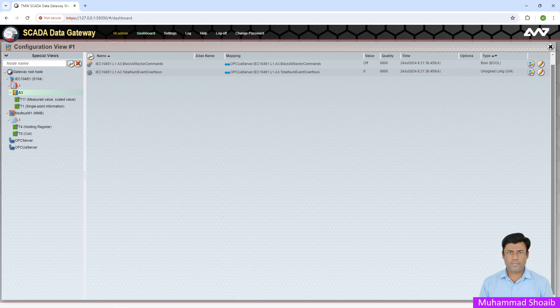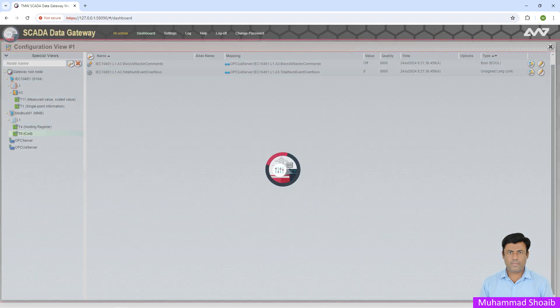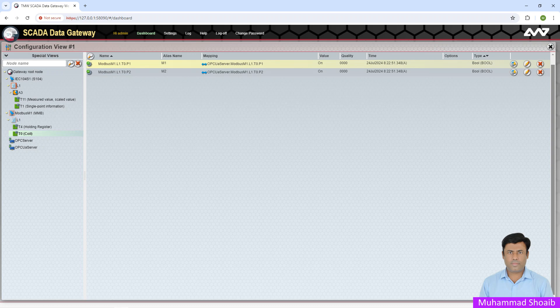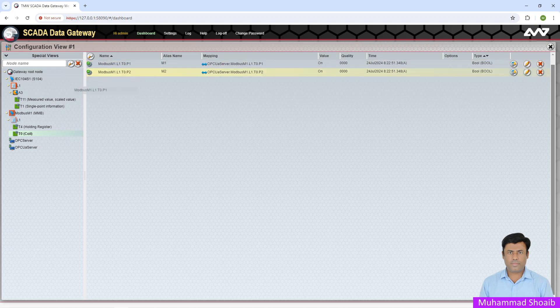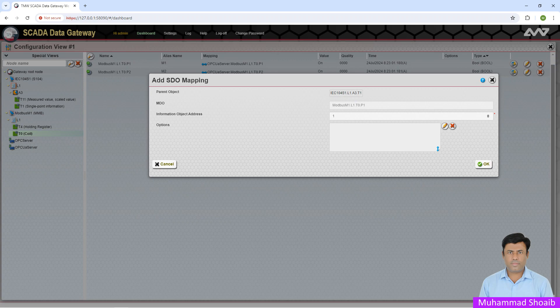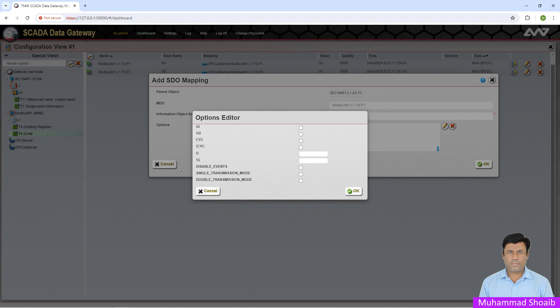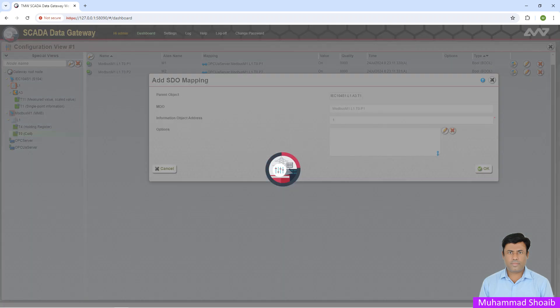Our next step is mapping between Modbus protocol and IEC 104 protocol — we'll do point-to-point mapping. Come to the coil, select your tag, then left-click, hold, drag and drop it onto the Single Point Information Object T1. Select your IEC 104 address for the single point. I'll keep the same value for the test and not modify any default values. Press OK. As you can see, it's showing a successful message.